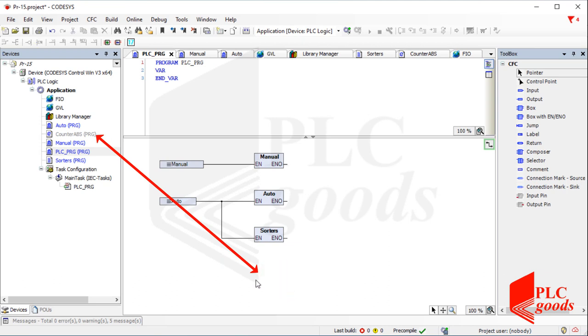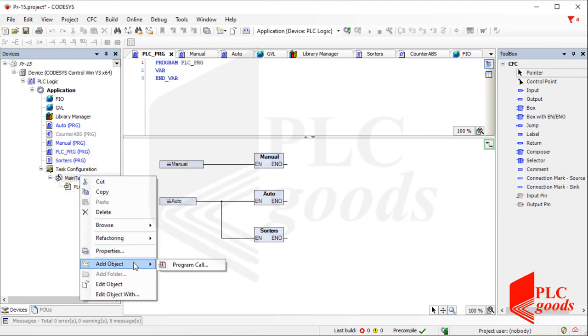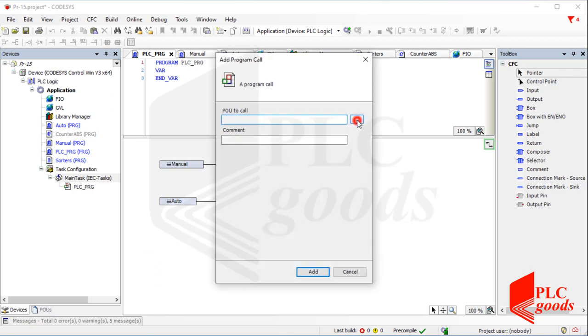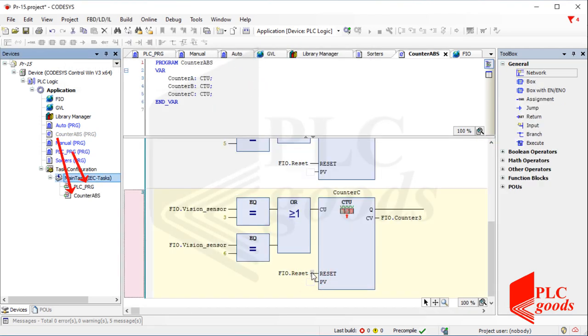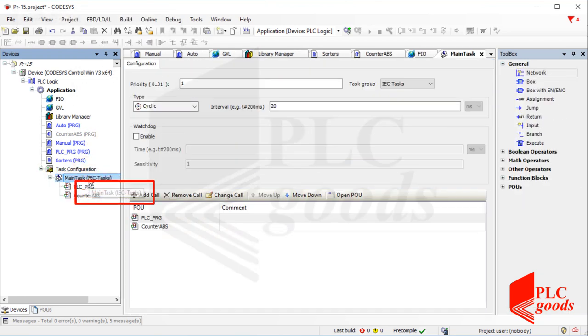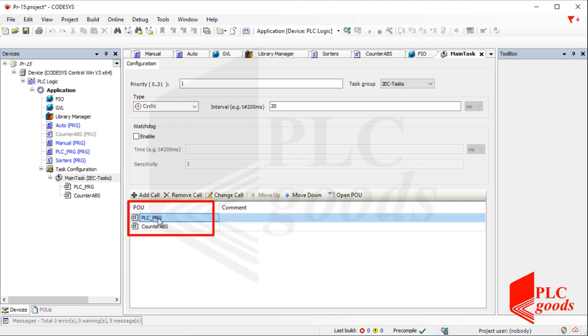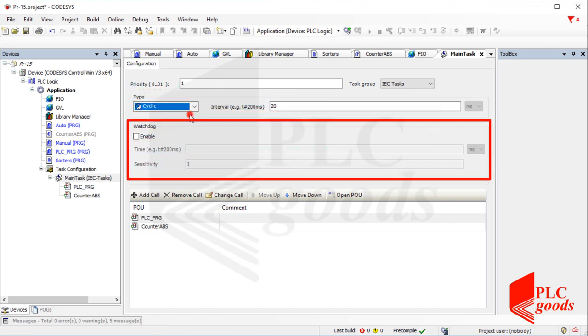Now let me show you another way to execute a POU directly. As you know, the controller starts its work from this POU. Now I want to add another POU. Here are two program organization units which will be executed by the controller directly; others will be called by the first POU. Note that if I click here I can change some settings such as the order between these two POUs, change its type, or activate watchdog ability, which will check the scan cycle time.